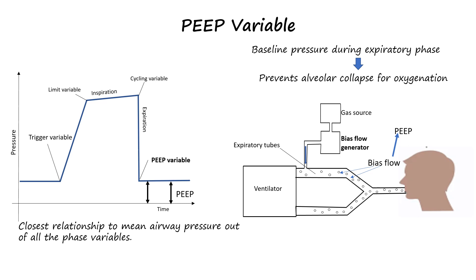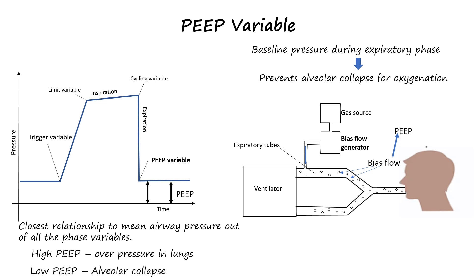Mean airway pressure is a common pressure monitoring parameter of mechanical ventilators that is closely correlated with mean alveolar pressure and represents stresses applied to the lung parenchyma during ventilation. If the applied PEEP is too high it can lead to overpressure of airways, and if too low, the alveoli can collapse and hamper oxygenation. The healthy lung should be ventilated with 5 to 8 cm H₂O of PEEP. The methods of choosing the optimal PEEP in various lung pathologies are discussed elsewhere.